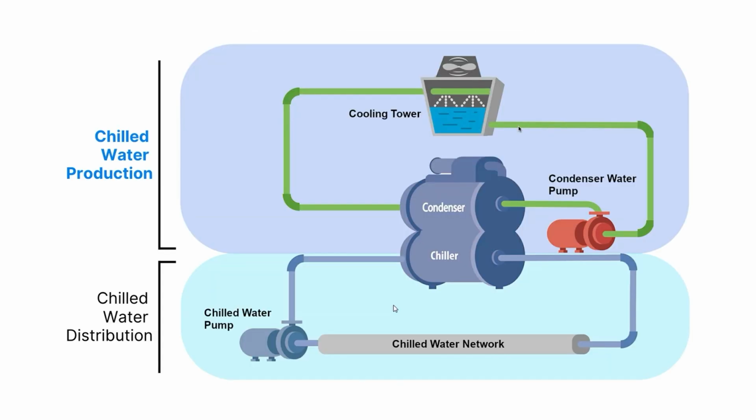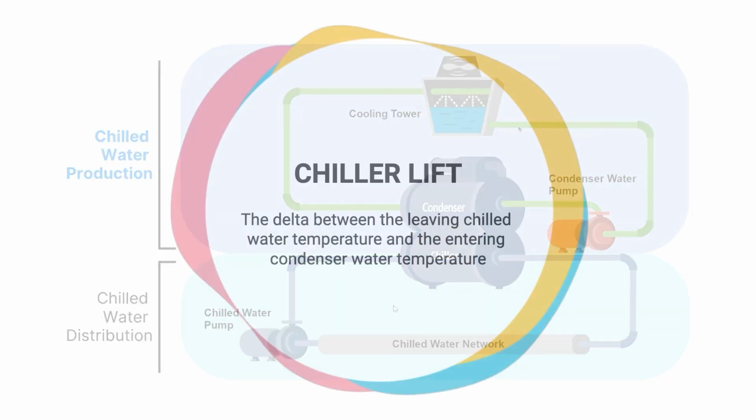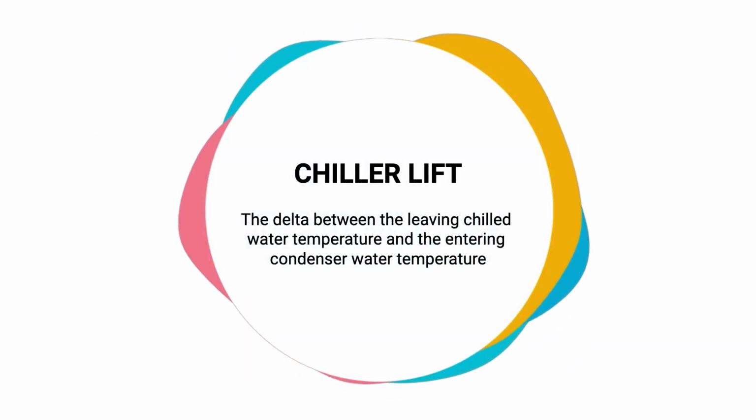But this is when we get into what we call trade-offs. That set point and condenser water temperature optimization is a really good example of this. That set point represents a trade-off between cooling tower fan energy and the chiller energy.